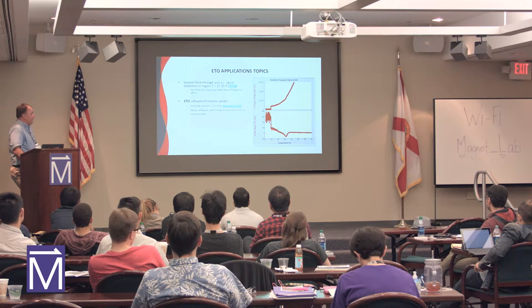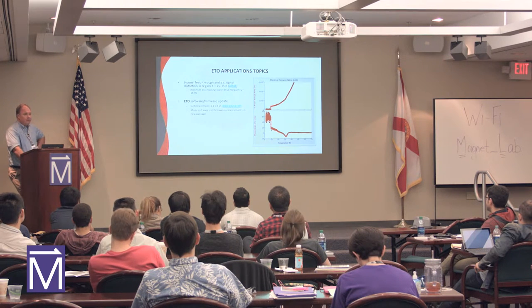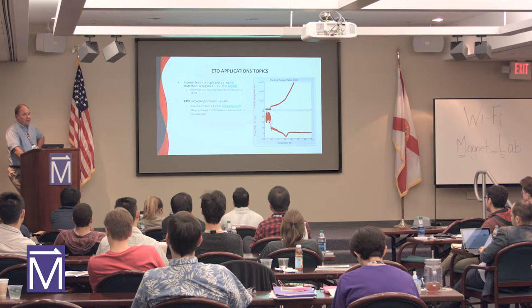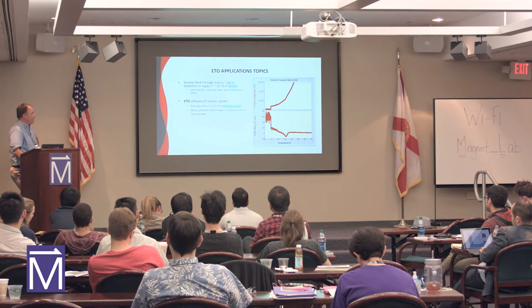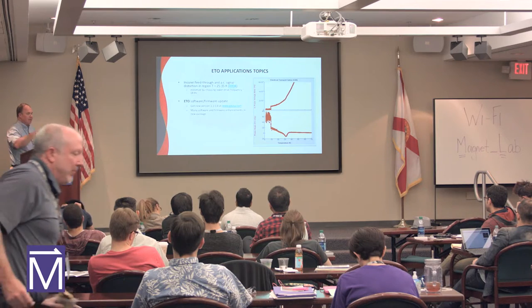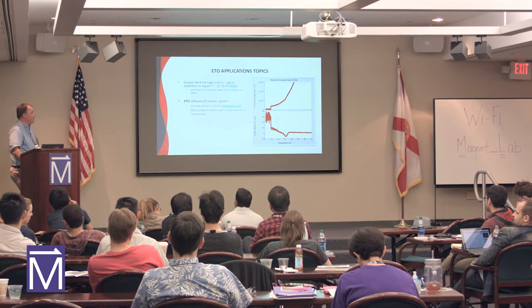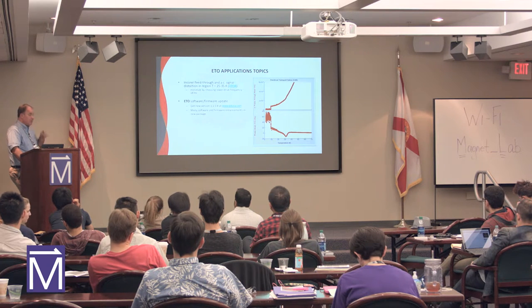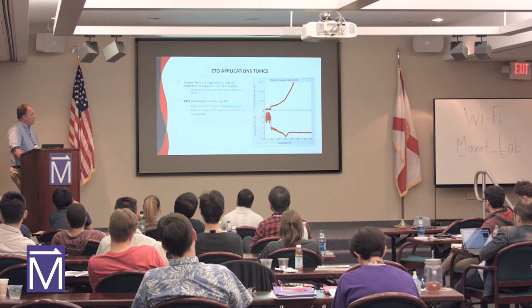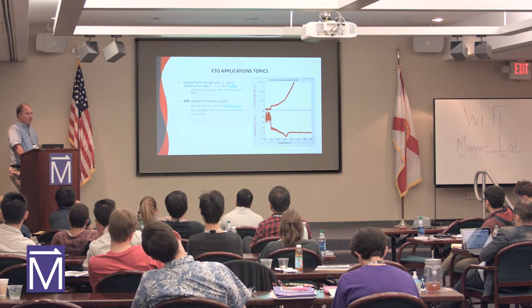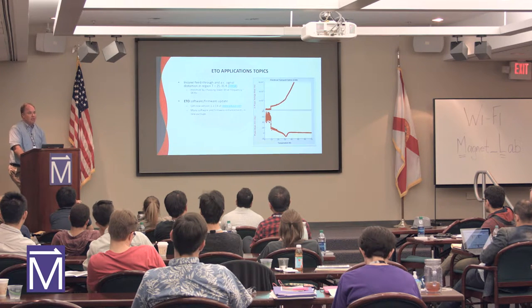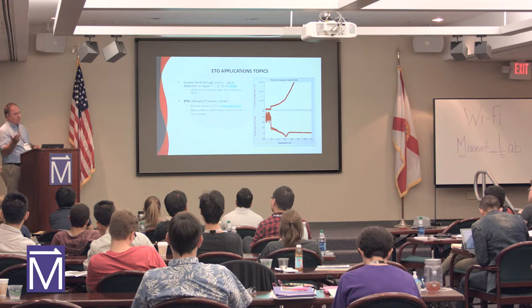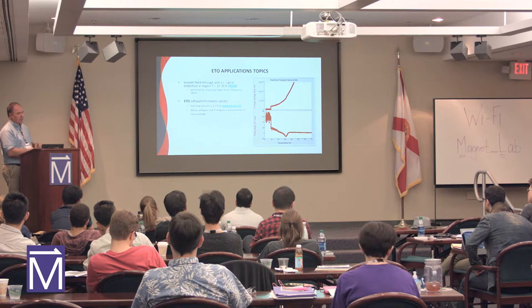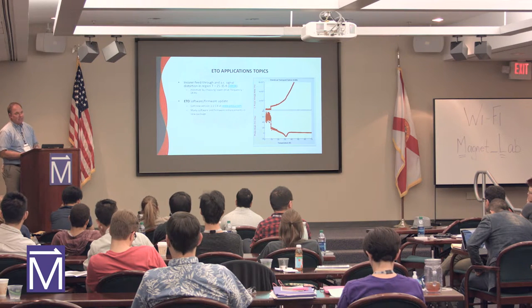We wrote an app note about the feed-throughs. The vacuum feed-throughs have Inconel in them, and the resistance change is a function of frequency. So there's an AC response to the resistance of the Inconel feed-throughs as a function of the system. So you can see this effect. You can't get away with it because you need to use these feed-throughs in the low temperature physics, right? You need these feed-throughs to keep things at low temperature. So you buy these things, you have the wires going through them. But they may introduce artifacts into your measurement.